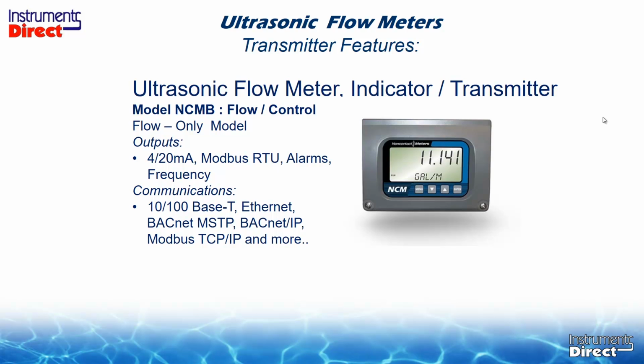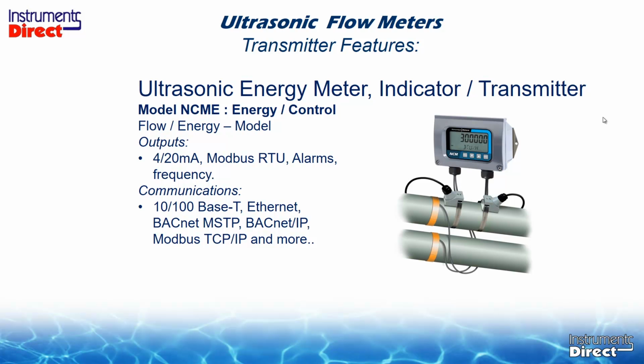The NCMB, which is the basic water meter, offers a local display and has standard outputs of 4 to 20 milliamp and Modbus RTU. The optional advanced communication models include communications of Ethernet, BACnet, the variations of BACnet, TCP/IP, and more. The energy module, which is the NCME, is a water meter plus the energy module, which allows you to read in BTU.